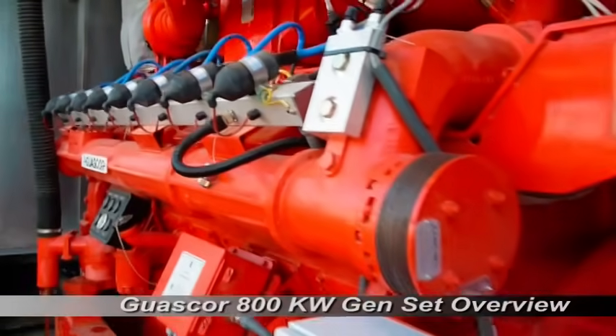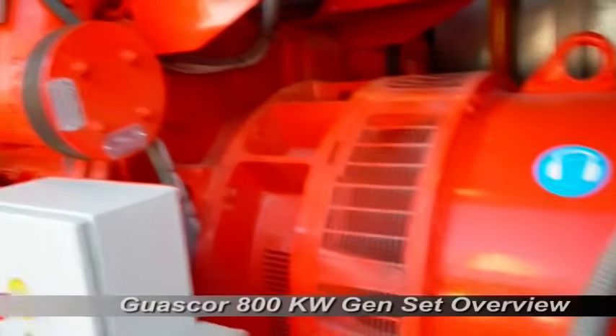The engines consume lube oil at a rate of less than 0.3 grams per kilowatt hour. The alternators have an apparent power of 875 kVA. Insulation class for the alternators is Class H, and heating is Class F. The alternators have a protection level of IP23.